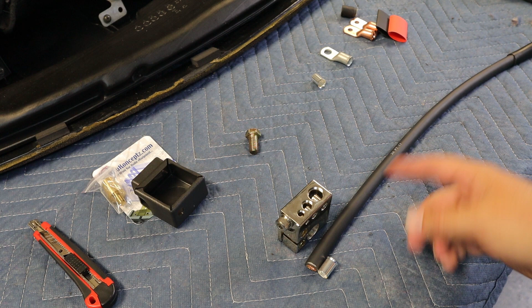For the other end of the ground cable, I need to prep it to go into the terminal. This has a set screw type connection. You could just strip the sheathing and stick the plain wire in there, tighten it down, and that in theory should work. But if you over tighten it, you could damage the cable, the copper wires.